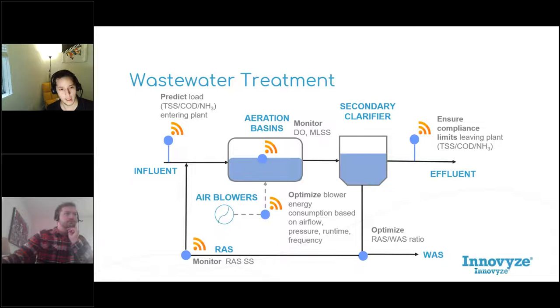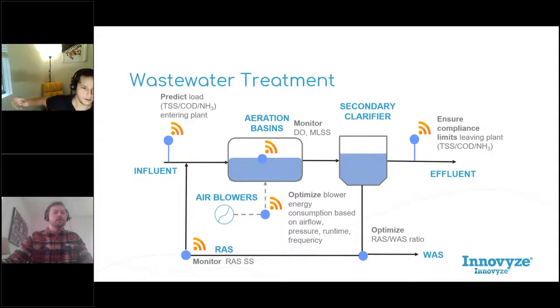I used to commission plants, but it's really hard when you have to go to the head of a plant, clear a bar screen, and now downstream you need to maintain proper disinfection levels. So what do you do while you're clearing a bar screen? You turn up your chlorine dose so you have enough time to go and come back, right? One good way to manage that is to set those schedules up front, predict with a 24-hour look ahead where we really need to be, and automate those calculations based off real influent water quality, so the operator spends less time thinking about where that needs to be.